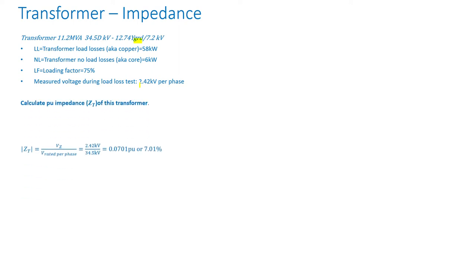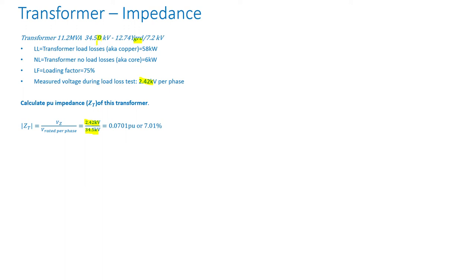Let's calculate the per-unit impedance. The magnitude of the impedance is the impedance voltage measured during load losses divided by the rated voltage of the winding where current is circulated. So it's 2.42 kV divided by 34.5 kV. Since this is a delta, the per-phase voltage equals the line-to-line voltage. If it were a Y at 34.5 kV, you would divide by the square root of 3. The result is 7.01 percent.